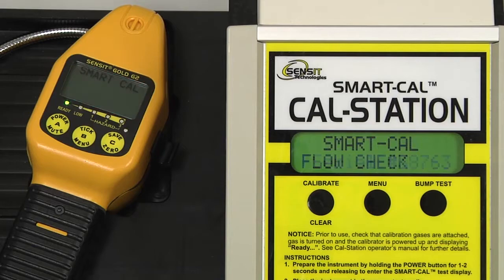It will display that our device has been found. It will do a flow check, followed by a 60-second purge. After the purge has been completed, the instrument will auto-zero and the calibration process will start. The first gas is 2.5% by volume methane, both for the internal TC sensor and the LEL sensor at the end of the gooseneck.